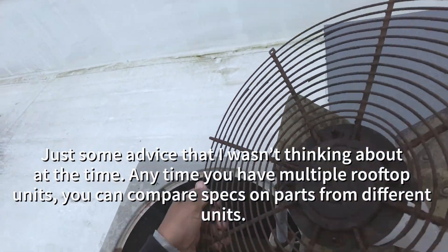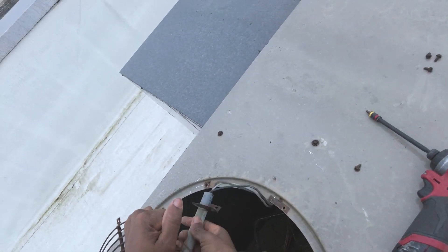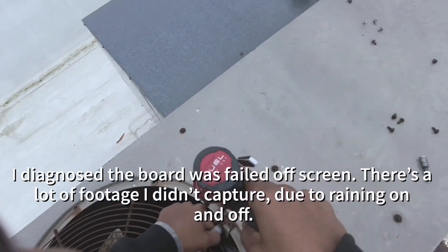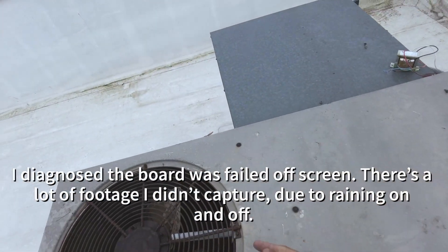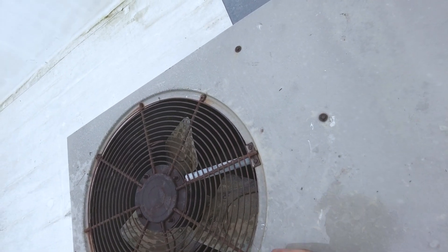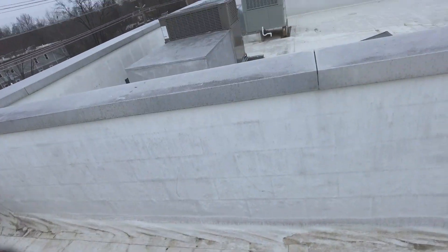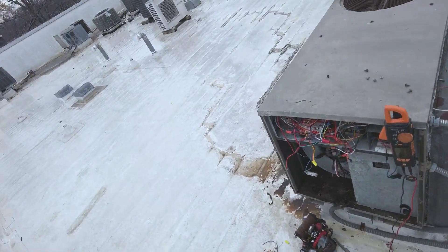Put this all disconnected, put it back on because I got that short rectified up there. More than likely what happened is that short killed the board — essentially the short that was on the suction line, the discharge vapor line. This is actually a 22-year-old unit, so the owner is holding on to it. Replacing it would require a crane, shutting down the whole street — it's a pretty popular street — so it's quite an expense.